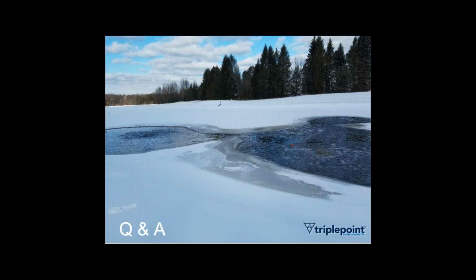In part because we're creating all this mixing around the unit, it's not going to bury itself in sludge, because it's constantly moving that sludge away. And so what we often see when you pull down a lagoon is almost like an area around the unit where there's very little sludge, like a very shallow crater, where it's sitting on top of the clay liner, and everywhere else around it is pretty open and sludge free. Usually that's creating a situation where it's not going to get stuck. And we've done this in lagoons with up to 10 feet of sludge in them. I haven't heard about any reports of there being any issues with getting them out.